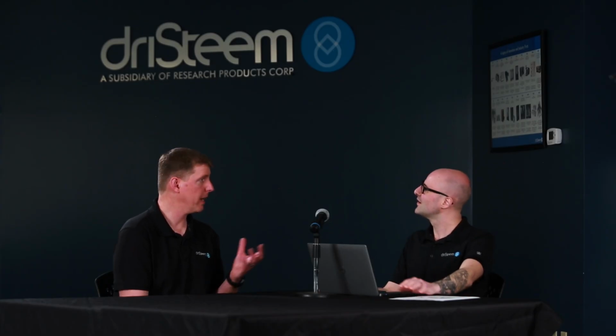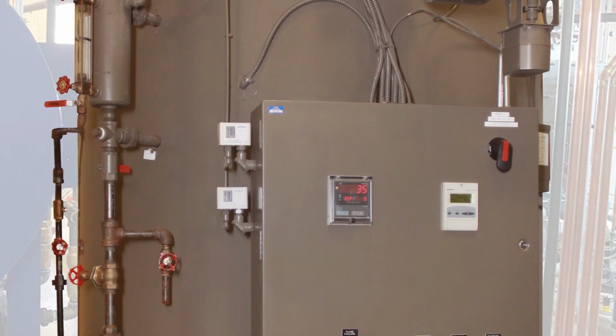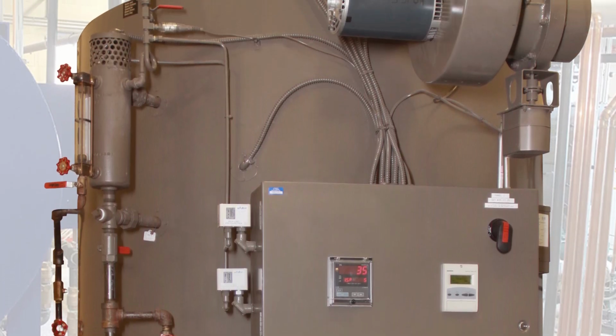So let's dive in. My first question for you is, what are the most common ways we can generate steam for humidification? Well, let's go back to isothermal dispersion, and this is where we want steam. As we talked about early on, if you've got a boiler available, tap into it. Now, you have to consider what is in the boiler. Are there corrosion inhibitors and stuff like that? Maybe I don't want to put that into the airstream that I'm breathing. Sure. So that's a consideration: I may have the boiler available, but I have to understand what's in it. If that's not a concern, or it's all good, it's just plain water, hey, disperse that directly.